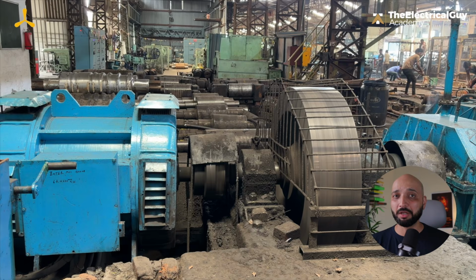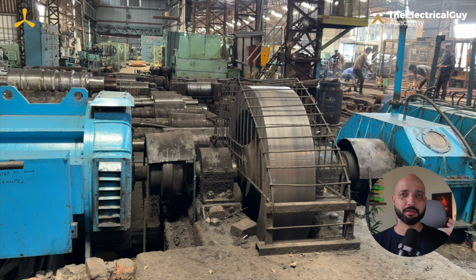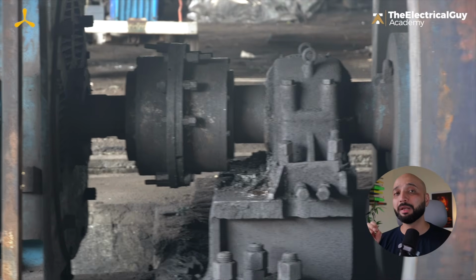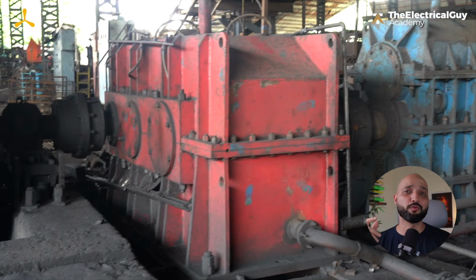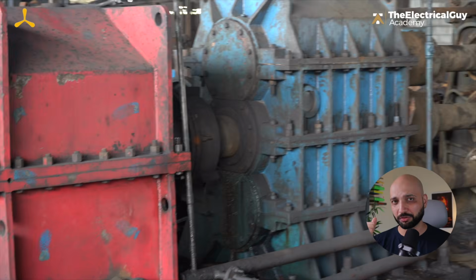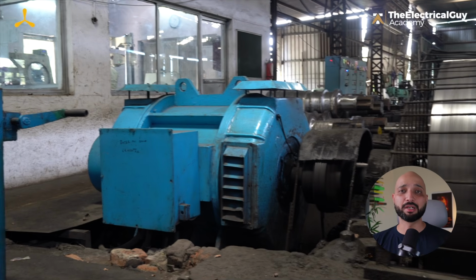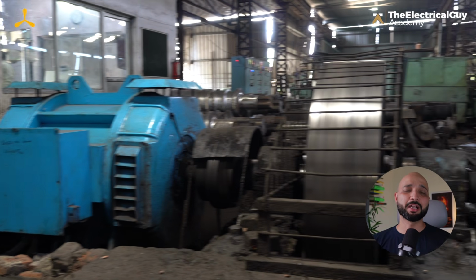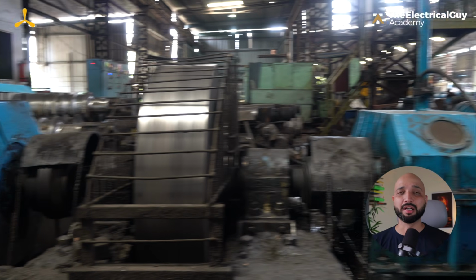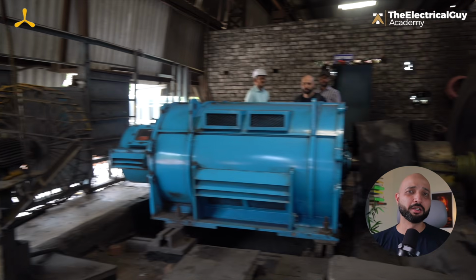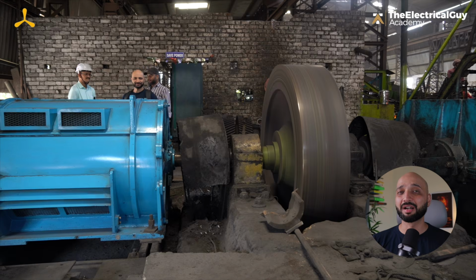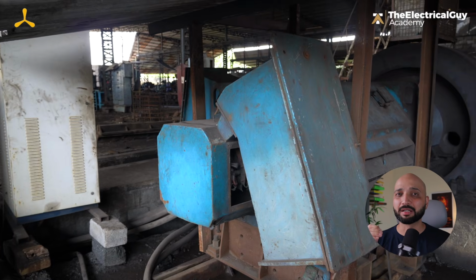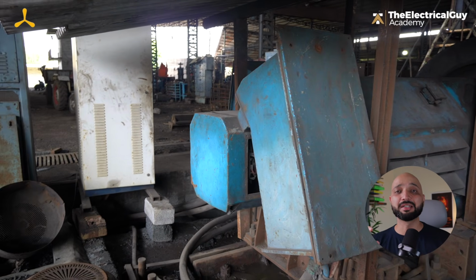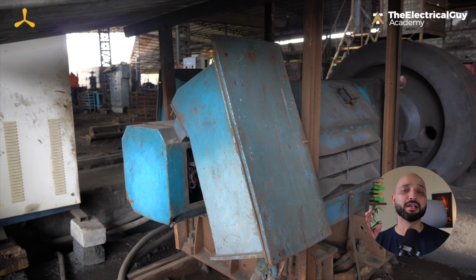Historically, and even today in many of the heavy rolling mills, slip ring induction motors, also known as wound rotor motors, are commonly used for such applications. The main advantage of slip ring motor is that the external resistance can be added in the rotor circuit during starting. This helps the motor produce high starting torque while controlling the starting current. And that is exactly what we need in a roughing mill.